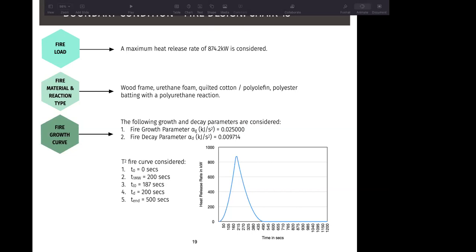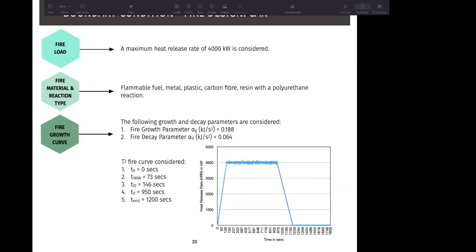So from 200 to 500 seconds, the fire will now decay and it will completely end at 500 seconds. So this now dictates your fire design for this particular item.